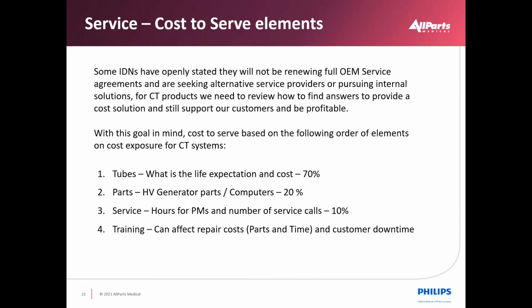So service for independent distributors, with regards to reviewing service agreements and the like, is that we see customers not always going with OEM service, using third parties or independent service companies to do service. We would call this multi-vendor service. And with these goals in mind, we have to have a weighting of what we would look at as a cost exposure. So in the case of CT, the first thing that I typically view is, do I have an alternate solution for glassware or for X-ray tubes, and knowing what the life expectancy is of a tube on a given product and knowing its cost. So that's 70% of my decision-making process with regards to an enablement of whether I should service that product or not.